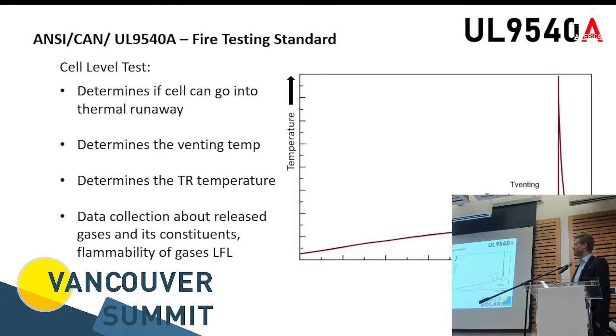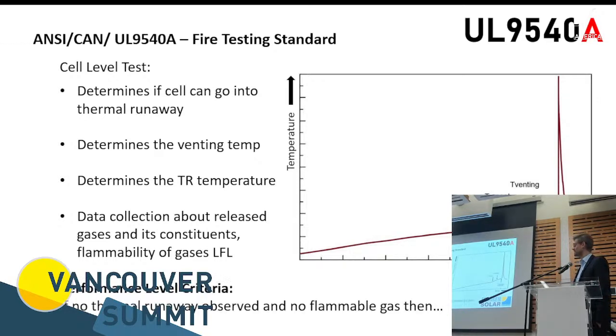The first on the cell level is, can the cell go into thermal runaway? And the answer is, for lithium, as I mentioned, yes, it will, because we just start heating at about 7 degrees per minute. And at one point, at a few hundred degrees, the cell starts to vent. And a little bit later, all of a sudden, the cell completely goes into thermal runaway and pretty much is releasing its energy. The testing will then see what is the actual venting temperature when that smoke or the gases are being released. And then it will collect data about what is actually being released and how flammable are those chemicals and that gas that is being released in that system.